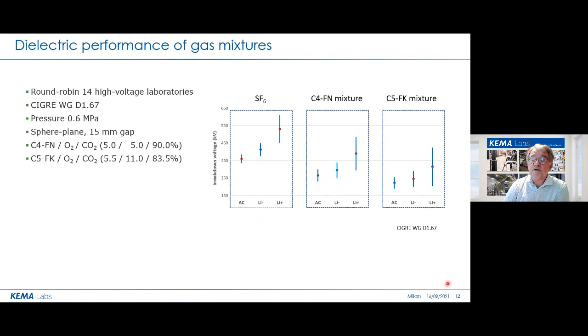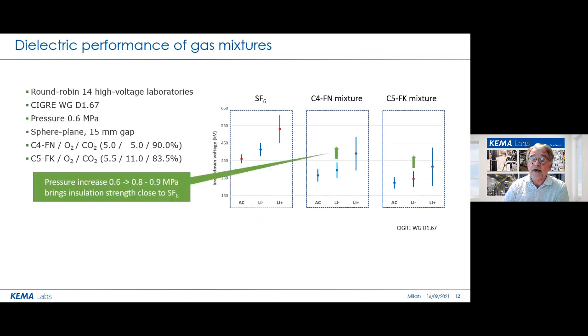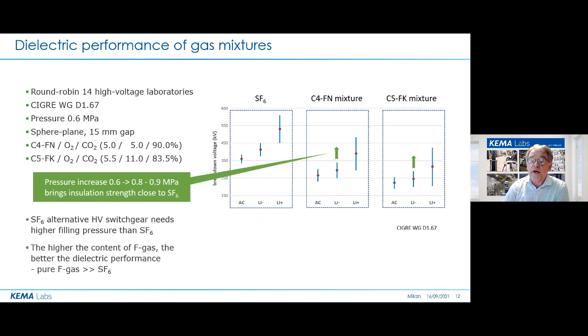As can be seen, the breakdown voltage for the new mixtures is lower than that of SF6 at the same pressure. And this is the reason that in the new products, the pressure must be increased, at least to come close to the dielectric performance of the SF6 gas. By the way, pure F-gases outperform SF6, but due to the thermodynamic constraints that we are going to discuss, they cannot be used in pure form and need to be mixed.